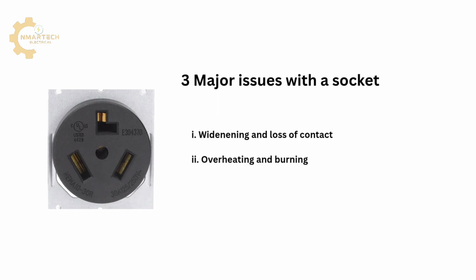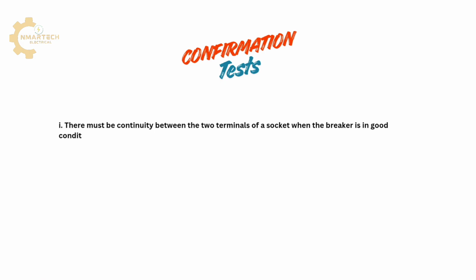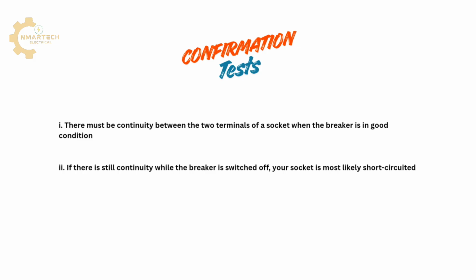Remember, when there is a short circuit, your breaker trips. There could also be disconnection from the coil. How do you confirm a socket problem? Under normal conditions, there should be continuity between the 2 socket terminals when your breaker is on. Now note that if continuity exists even when the breaker is off, please know that the socket is shorted. Remember to always switch off your generator before conducting a continuity test.